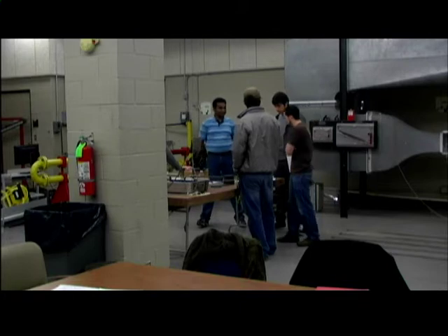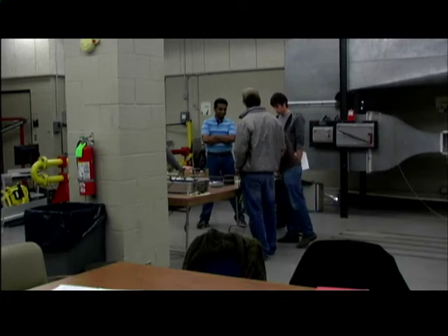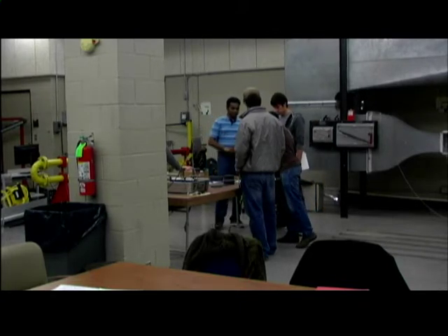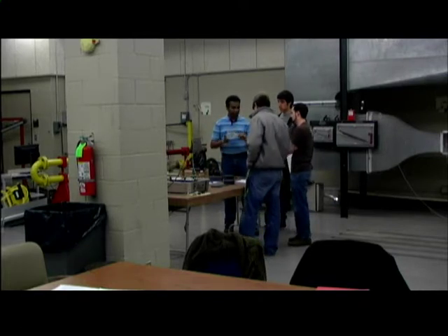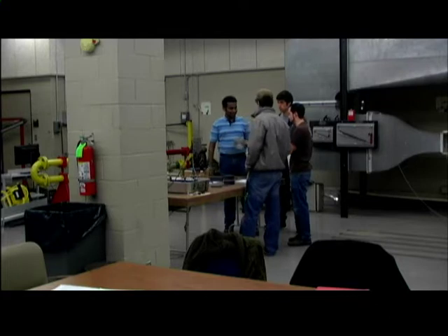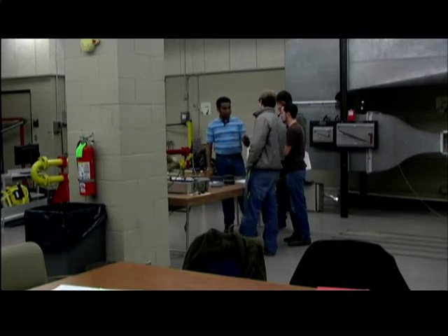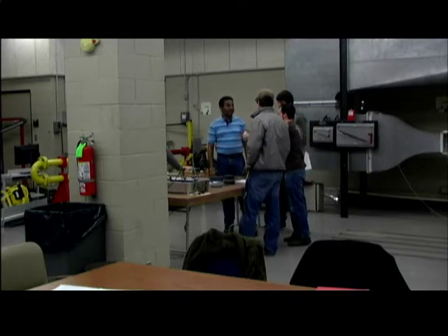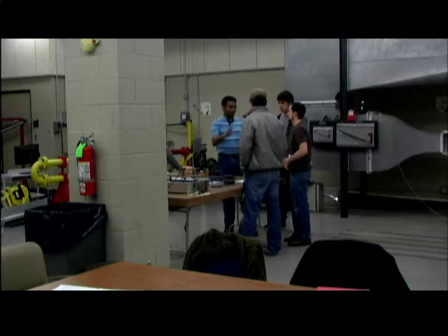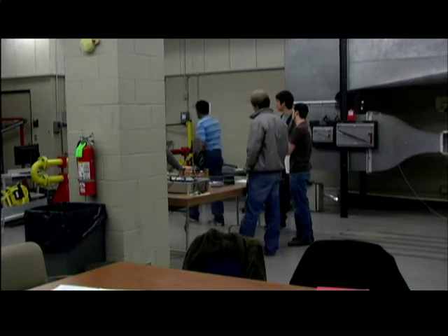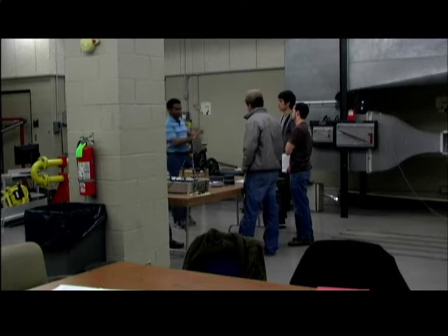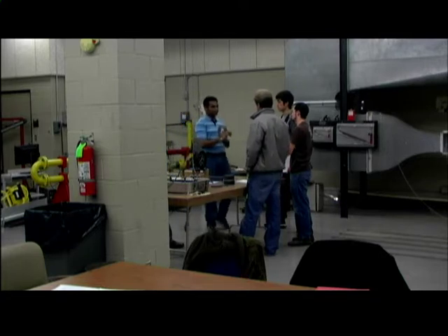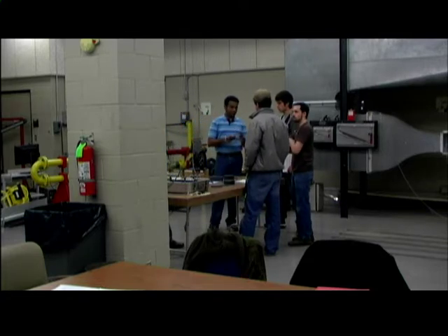Well, when do you measure it? How does it sit? Like this? Okay, now that's the question again that I need to ask. Which side should be on the upstream side? So the flow comes in this apparatus from here to there. So this is the upstream, this is downstream. So your bevel side should be facing the downstream. Okay, that's good.